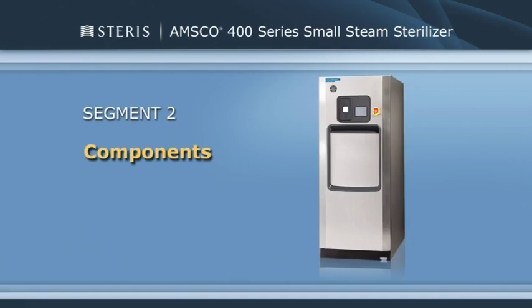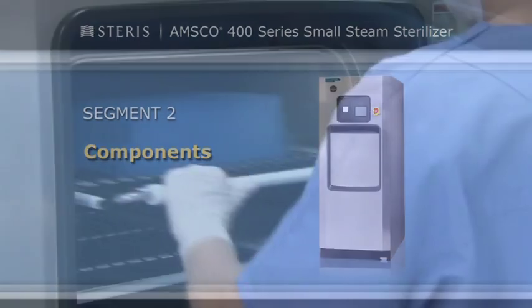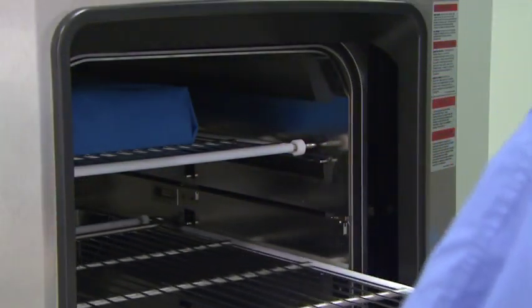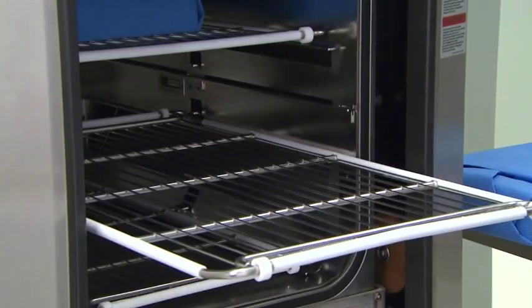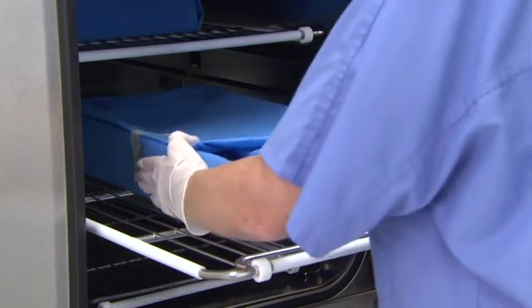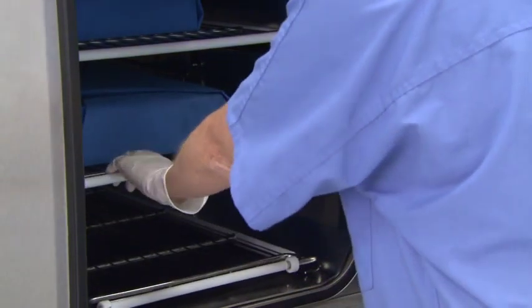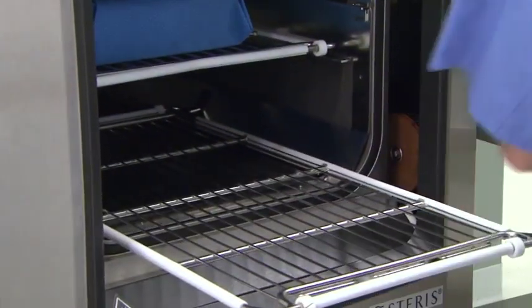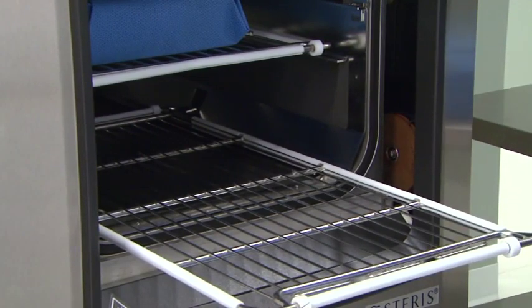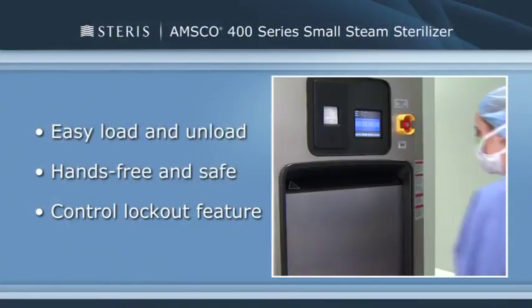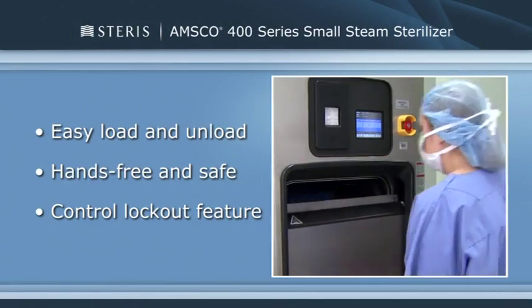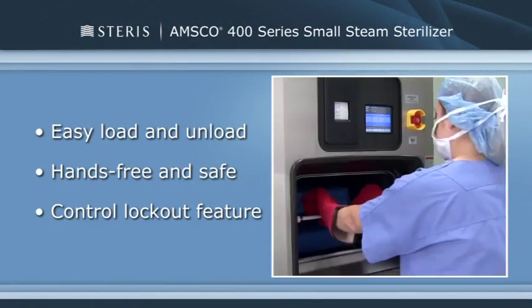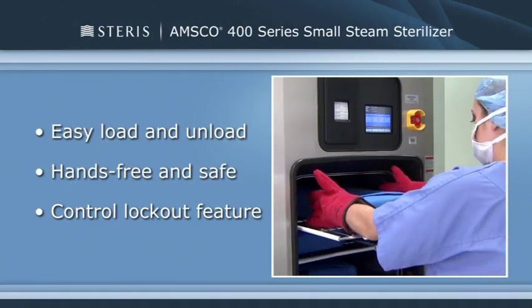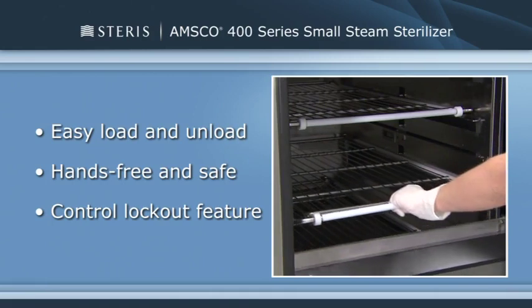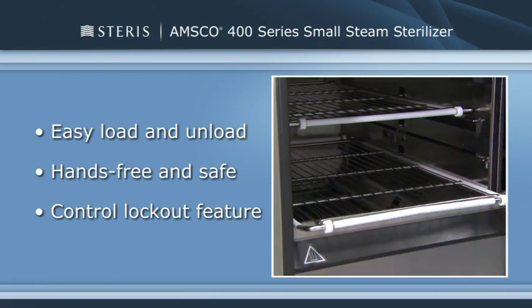The AMSCO 400 series sterilizer is available in two different sizes: a 16 by 16 inch chamber that accommodates up to two 25-pound sets or 4 fabric packs, and a 20 by 20 inch chamber that accommodates up to 3 25-pound sets or 6 fabric packs. The AMSCO 400 series small steam sterilizer was developed to fit into the surgical suite and was designed for easy load and unload. It features a hands-free open and close door, adjustable shelves, and a non-heat conducting door design for operator safety. The door stops automatically upon obstruction, and the control lockout feature prevents a cycle from starting if the door isn't sealed.